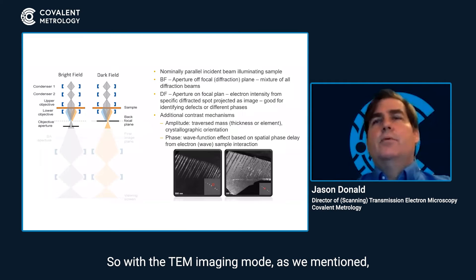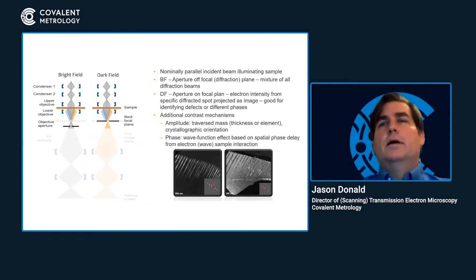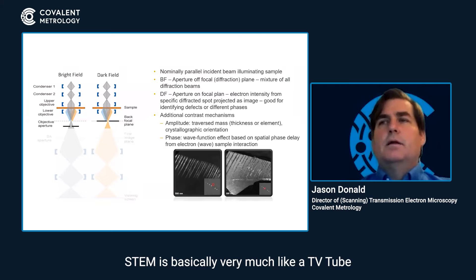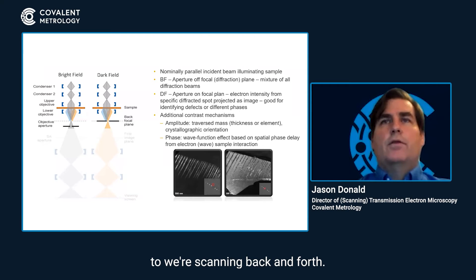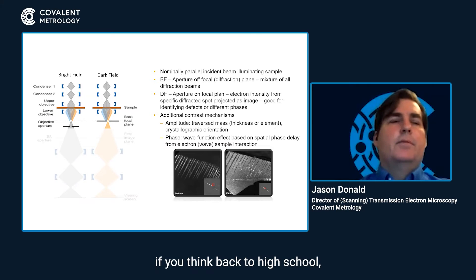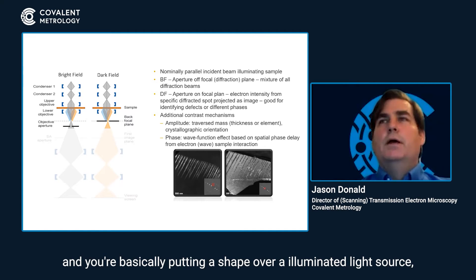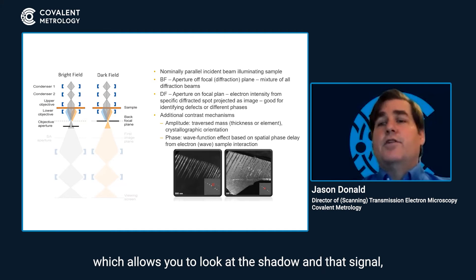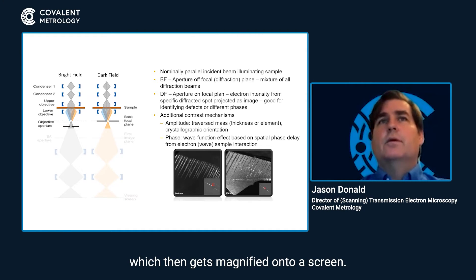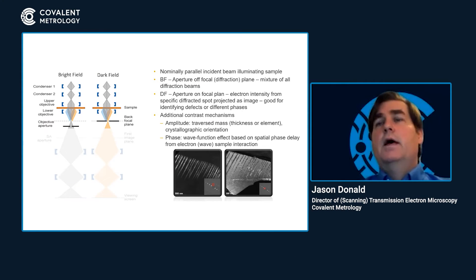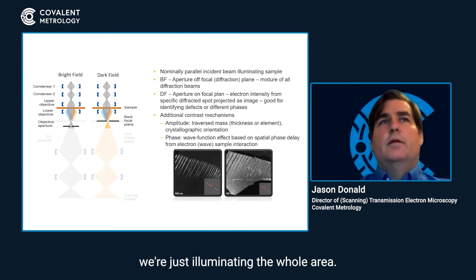With the TEM imaging mode, we also have bright field and dark field. This differs from STEM in that STEM is basically very much like a TV tube where we're scanning back and forth. TEM — the best example I can give is if you think back to high school of those transparencies a teacher would use. You're basically putting a shape over an illuminated light source, which allows you to look at the shadow and that signal, which then gets magnified onto a screen. Same thing as what's going on with TEM — it's a flood of electrons over a wide area, and we're not scanning back and forth; we're just illuminating the whole area.